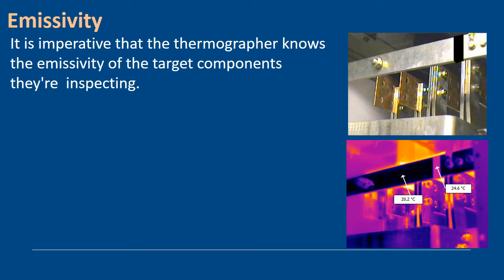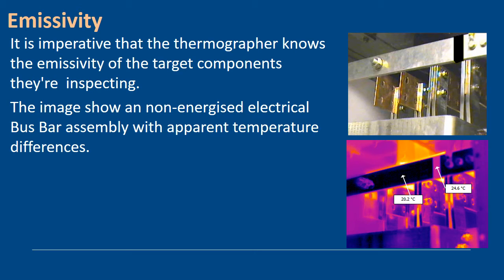If we look at the infrared image, we can see that basically it looks like we've got temperature differences, but this image shows a non-energized bus bar assembly with apparent temperature differences. This is actually in the manufacturer so it's never been turned on. If you look at the electrical tape on the infrared image, you can see there I have a reading of 24.6, but the bus bar section here, the shiny bus, looks much cooler because it's reflecting a background temperature.